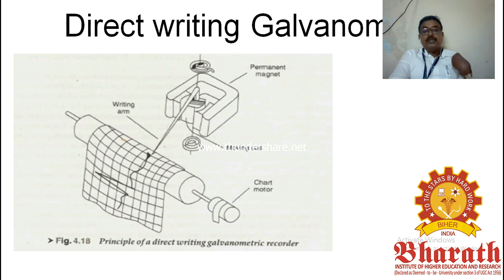What happens is you will have a permanent magnet, then a moving coil. That moving coil is going to have a writing arm. My input signal from the patient or the measurand is given to the permanent magnet moving coil. I already have magnetic lines of flux here. When I give some current to the moving coil, both the fluxes interact with each other, since the input current also produces some flux. Due to the interaction of both these fluxes, the writing arm will move over the strip chart, in x and y directions, and the chart motor will also rotate. This in turn gives the value of the biosignal, so the biosignal is recorded here.